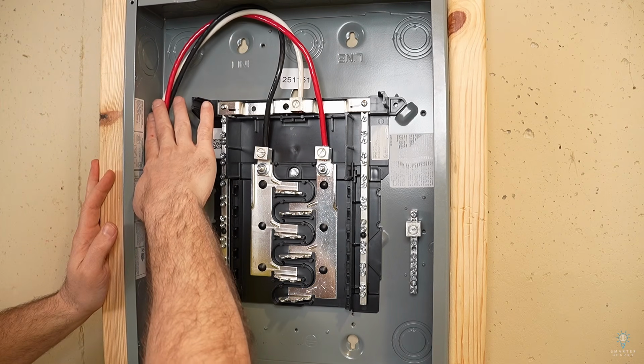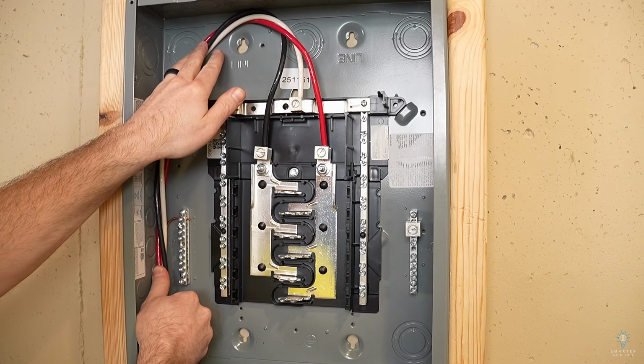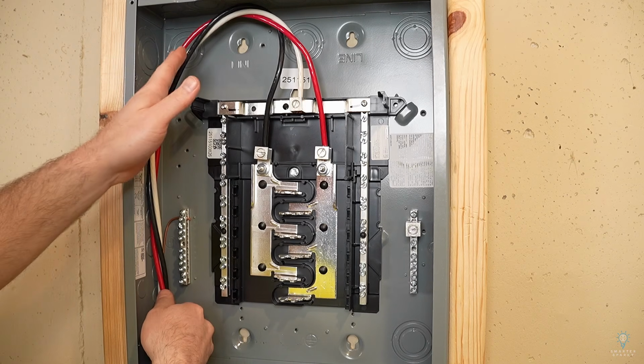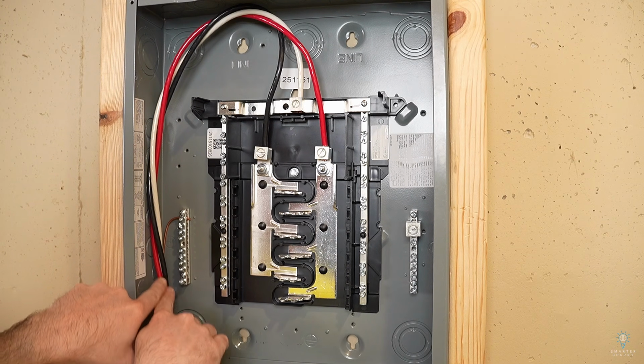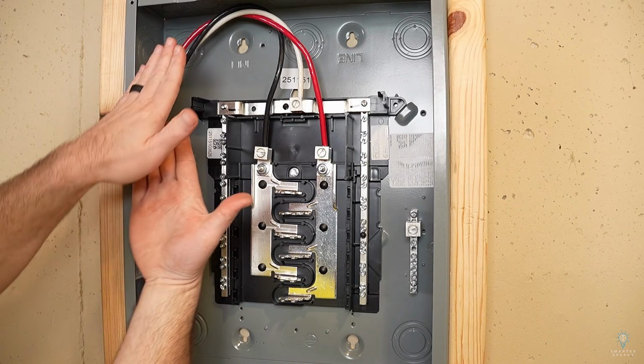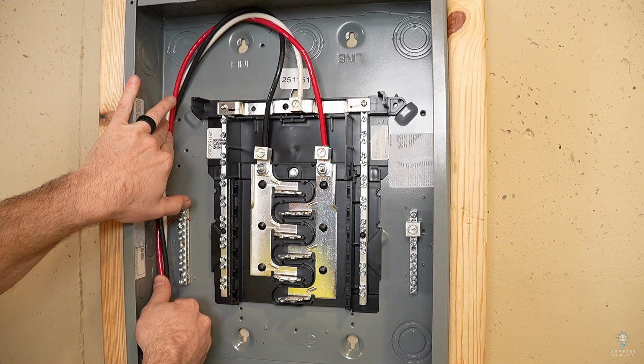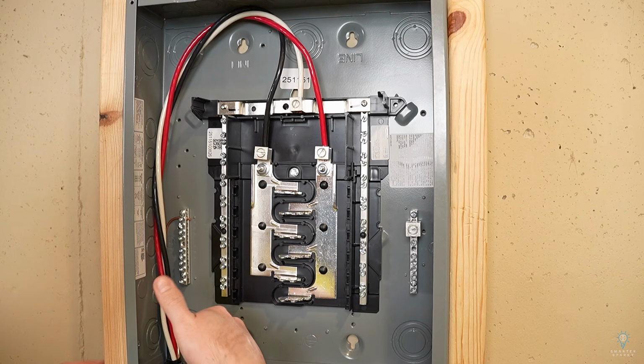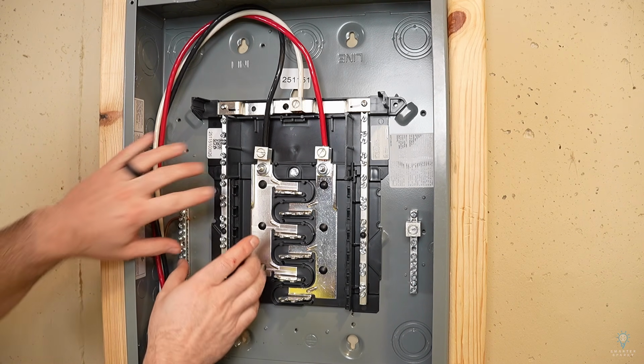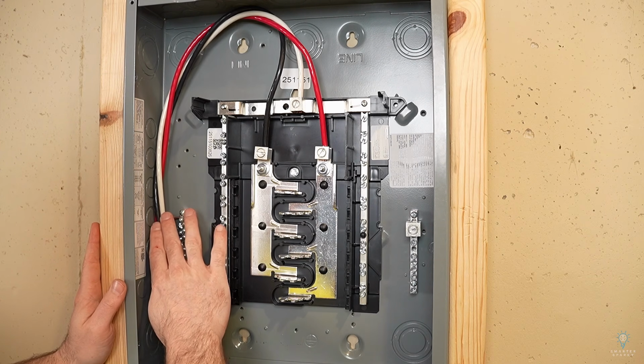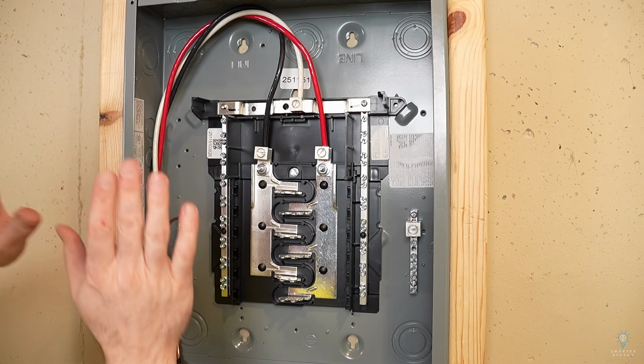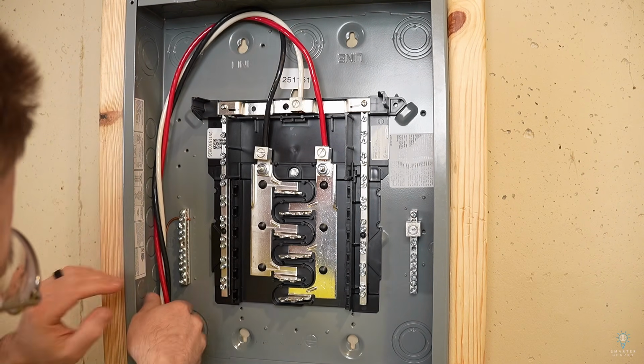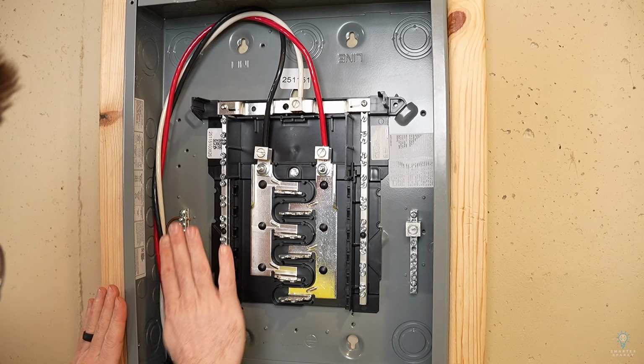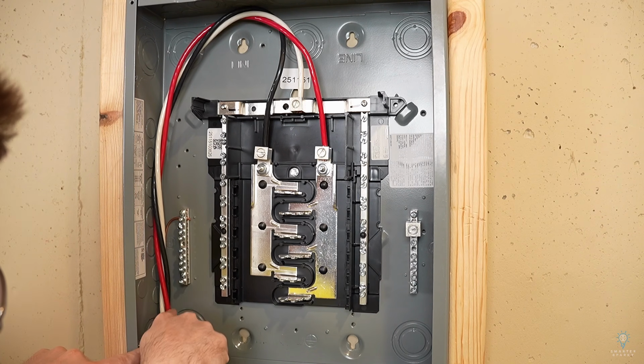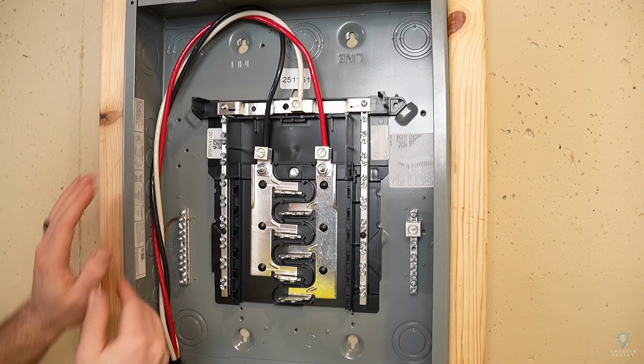But in this case, I'm just gonna give this wire a little bit of persuasion to go more towards the back. We don't have to get it all the way back perfectly, just so long as it's not sticking towards the front. And really, if we just put a bend right down here, that's gonna be more than enough to keep that wire towards the back of the panel. As we bring branch circuits in here, they're gonna lay on top of that anyway, but I would say that's pretty good now. That wire is wanting to stay towards the back. Again, all we have to do is put a little bit of a bend right down here, and that will help push everything back.